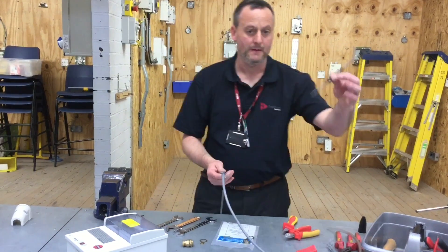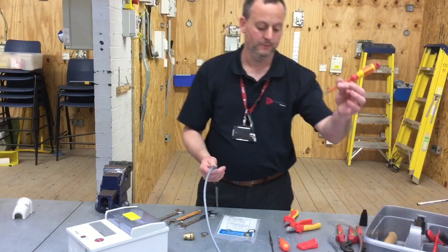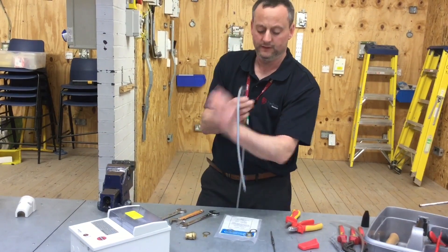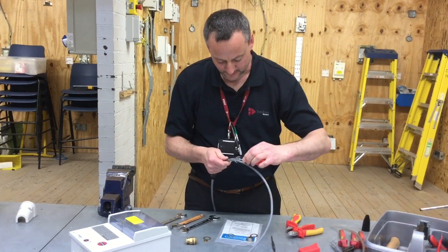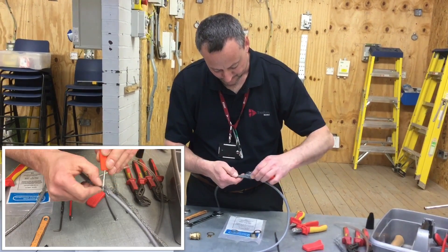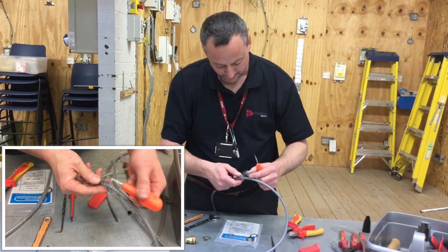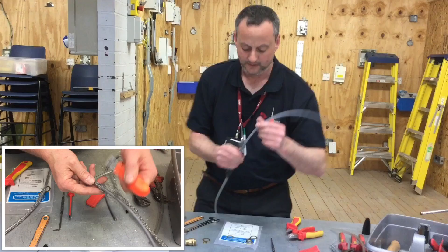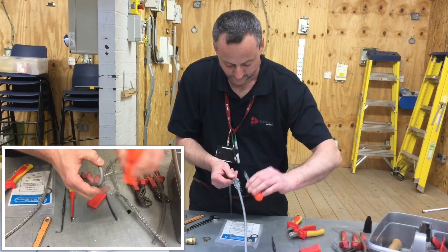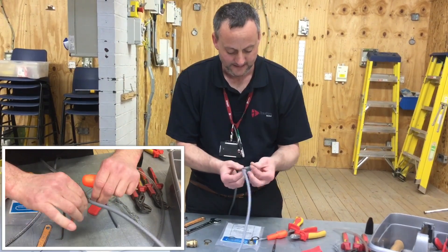We're going to open that out using a scriber — in our case a bradawl — or a terminal screwdriver from our toolboxes. We're going to do a 50-50 split: take the bradawl down, separating out the strands on one side, then go round to the other side — 50% of the way round the cable — and separate the other side, so we have approximately half the braiding either side.